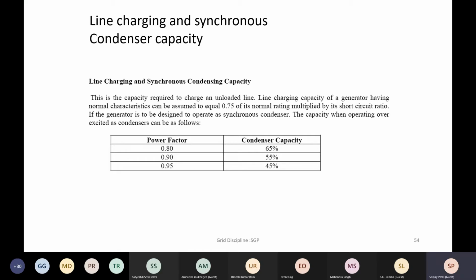Then comes the line charging capacity and the condenser capacity of the machine. Now, the grid code also mandates that hydropower stations especially should have the capability to operate in condenser mode. At least the power stations which are 50 megawatt and above should have the ability to operate in condenser mode. What it means is that your turbine side, the hydraulic side, will just be turning in the pit. So the resultant losses should not cause any damage to the turbine, while the condenser operates only generating reactive power. So it acts as a synchronous condenser, meaning it can export reactive power or it can absorb reactive power.